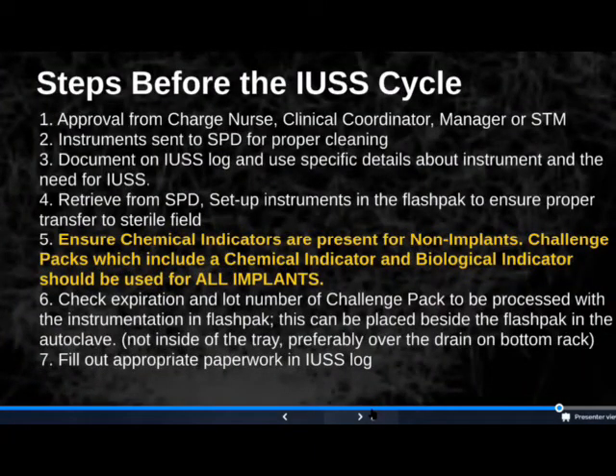So the steps before the IUSS cycle: approval from the charge nurse, clinical coordinator, manager, or STM. Instruments are always sent to SPD for proper cleaning. We do not use the sinks upstairs or any of those types of other methods. It must go down to SPD. Document on the IUSS log and use specific details about instruments and the need for IUSS. Retrieve from SPD, set up instruments in the flash pack to ensure proper transfer to the sterile field. Ensure chemical integrators are present for non-implants.